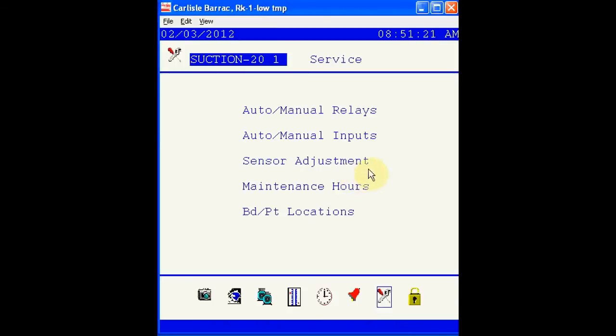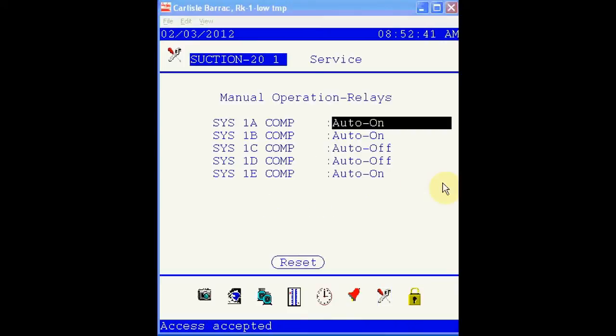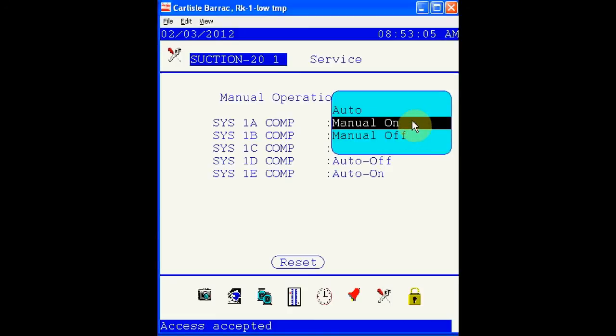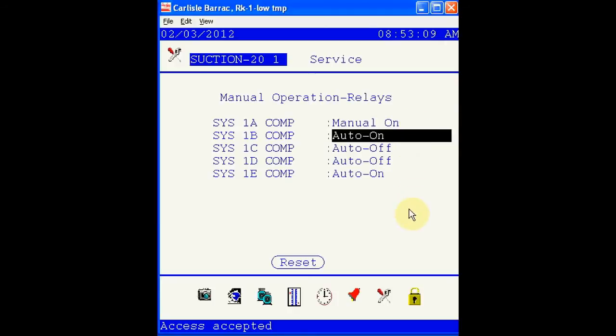Options that you have such as overrides, which can be done with auto manual relays or auto manual inputs, or even sensor adjustments. Let's take a look at auto manual relays. If we need to override a compressor, in this case, it can be done through the auto manual operation. To do this, you would use your edit key to highlight the compressor you need to override. Let's say we want to override system 1A compressor in the on position. Select manual on, and the compressor will be overridden on.